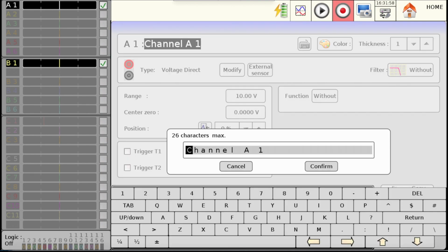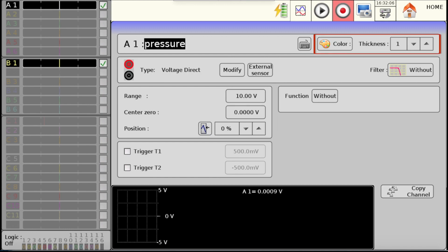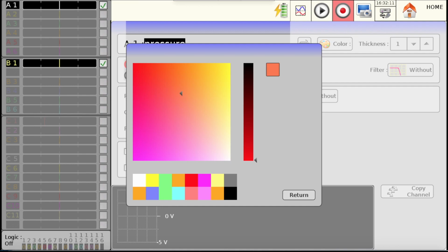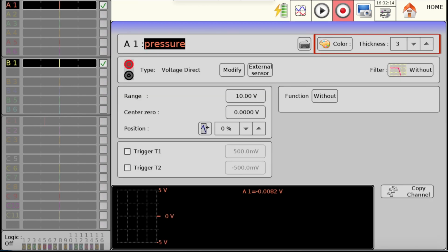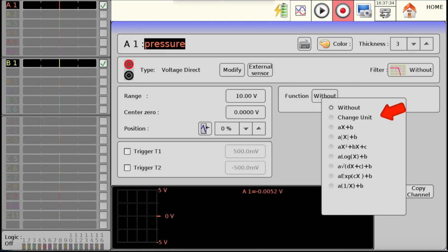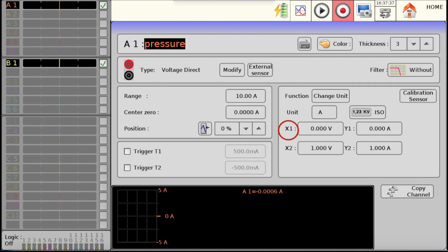Let's name this channel Pressure. You can configure the color and the thickness of the measurement curve. Then, let's activate the change of unit function and define the slope of our signal, x1 and x2 being the voltage values measured by the instrument, and y1 and y2 being the physical values. Let's set the unit in bar.